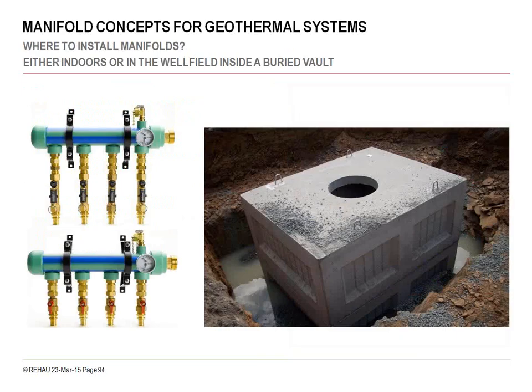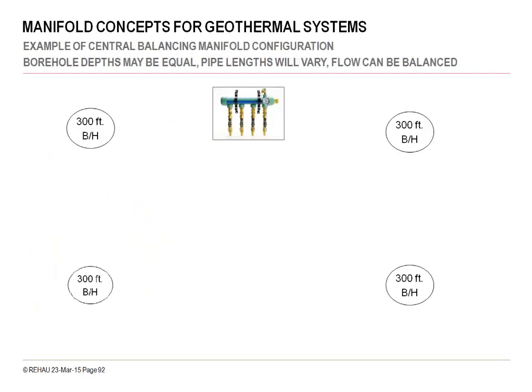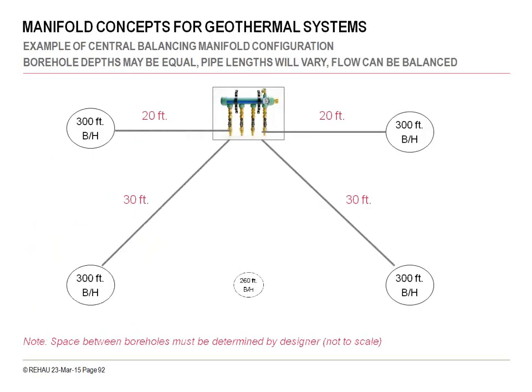Just another image. These balancing manifolds can be located in a mechanical room, depending on the proximity of the borehole field, or in some cases, in a precast manhole vault. You'd have the balancing manifolds installed inside the vault, and then you would have, say, 4-inch or 6-inch mains, supply and return mains, coming from the vault, going into the mechanical room to the pumps. So with that ability of being able to set the flow of each borehole, now you don't have to be concerned about this plus or minus 5% length that I mentioned in the reverse return headering.